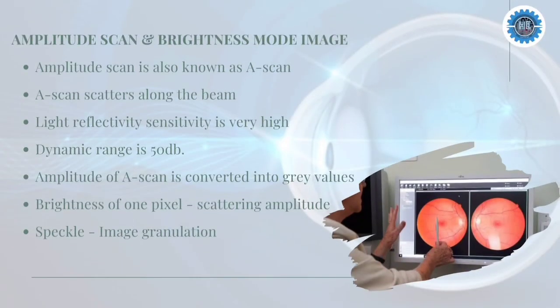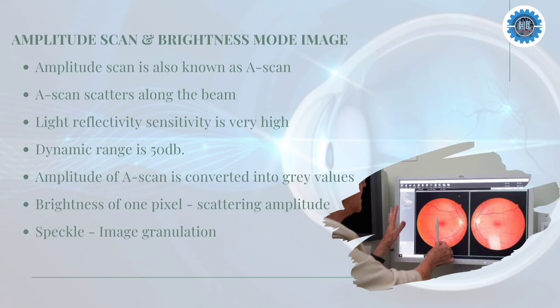The third principle of OCT is the Amplitude Scan and Brightness Mode Image. The envelope scan of the interference signal detected is called the Amplitude Scan, also known as the A-Scan — the same terminology as in Ultrasound Sonography. The A-Scan is a depth profile of scatterers along the beam. The first surface reflection of the tissue forms the highest peak, and different layers in the tissue may be responsible for different amplitudes. Because sensitivity for light reflectivity is very high, amplitude scans typically cover a dynamic range of more than 50 dB.